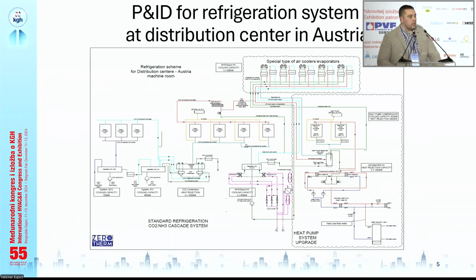This slide represents a simplified P&ID for this particular refrigeration system that we installed in the distribution center in Austria. This was done in cooperation with Johnson Controls. As you can see on the left side, this is just the standard refrigeration CO2 ammonia system that has minus 36 evaporation temperature, around 750 kilowatts of cooling power. And we have a dry suction going to 3 piston compressors.